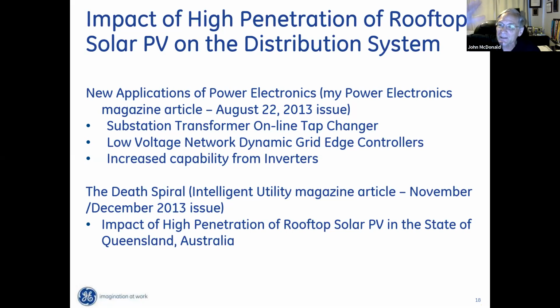And then it oscillated. This poor tap changer, trying to keep the secondary voltage constant, was now operating over 120 times per day. Its expected lifetime went from 35 years to less than 2 years — it would have to be replaced. So I wrote this article in Power Electronics Magazine 8 years ago.